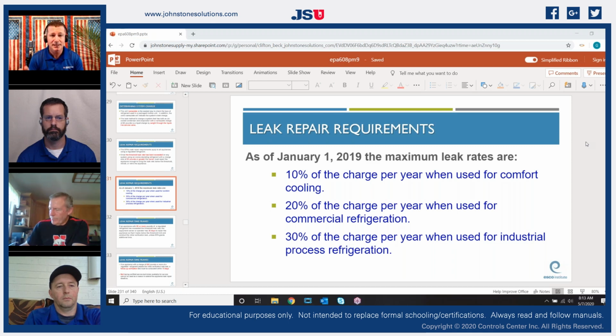It's all about keeping these, and this is all of our exempt refrigerant or non-exempt refrigerants. So anything that has the fluorine and chlorine, our HFCs, our HCFCs, CFCs if you happen to run into them. So if it has a fluorinated or chlorinated refrigerant, we're just now saying, hey, you can't just let these things leak anymore. If it's an industrial system, it's used for industrial manufacturing and processing. If it's a 100-pound system and it leaks 30 pounds within a year, they are now required to fix that, and you are required to inform them of that leak. That's what this 10, 20, and 30 is pertaining to. So, in the days of old, if a system had a leak on it, it wasn't required by law to fix that leak. It now is going to be required by law to be fixed or to actually be condemned. And we'll talk about that a little bit more as we get into our type 3 requirements.